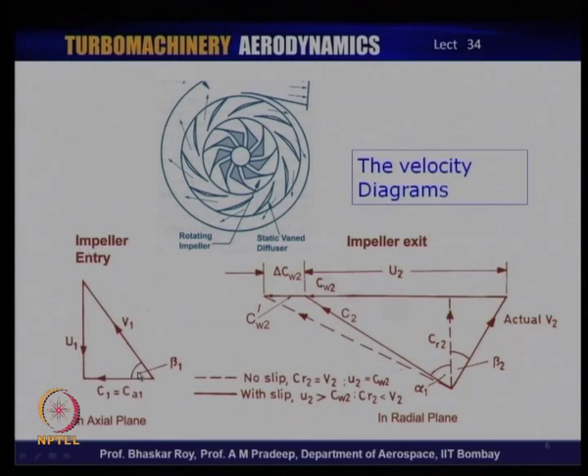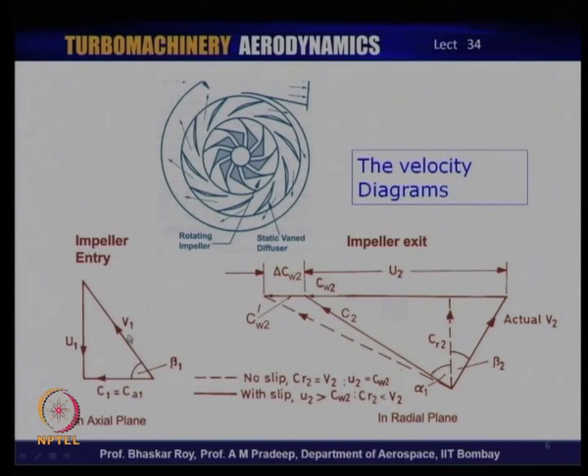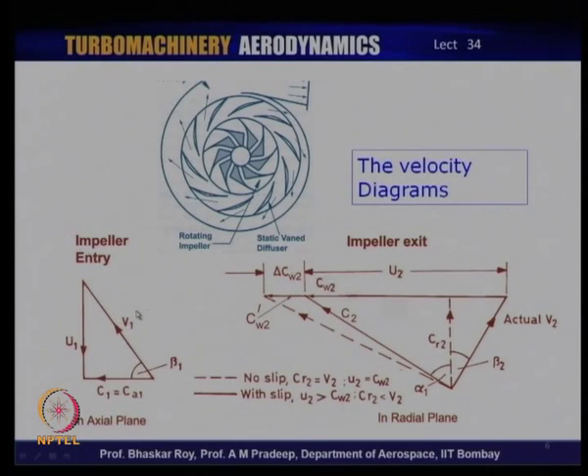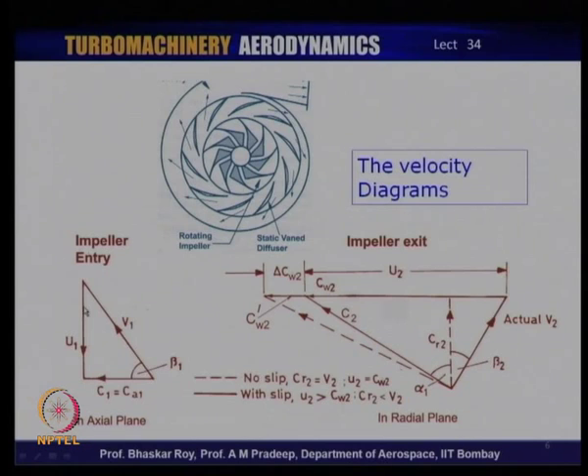In the case of modern centrifugal compressors rotating at very high speeds, it is entirely possible that V₁ actually goes supersonic. By design, designers try to avoid supersonic flow going into the inlet of the centrifugal impeller. When V₁ at the eye tip goes supersonic, one may consider putting an inlet guide vane there to turn the flow away — meaning the axial flow is turned so that the velocity V₁ is reduced from supersonic to subsonic. This is a simple trick: if the calculation shows that V₁ could go supersonic, the inlet guide vane could turn the flow the other way so that V₁ again becomes subsonic.